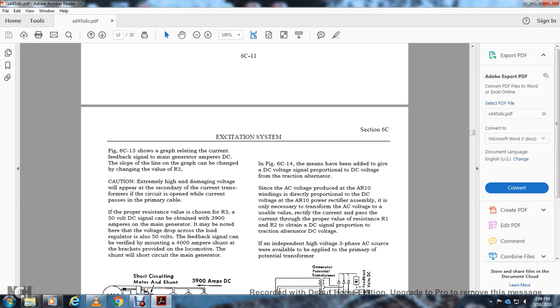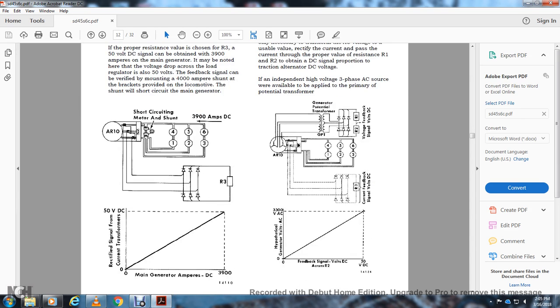It is only necessary to transform the AC voltage to a usable value, rectifying the current through the proper value resistance, resistor R1 and R2, in parallel or in series, to obtain the DC signal proportional to the traction alternator DC voltage. In addition, with a high voltage 3-phase AC source, we were able to apply the primary potential transformer.